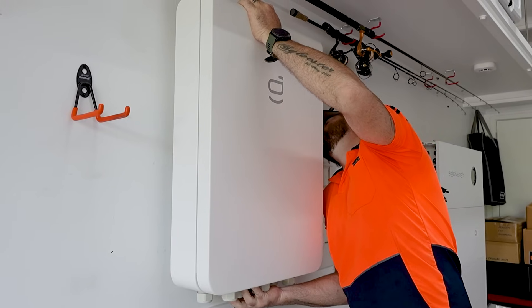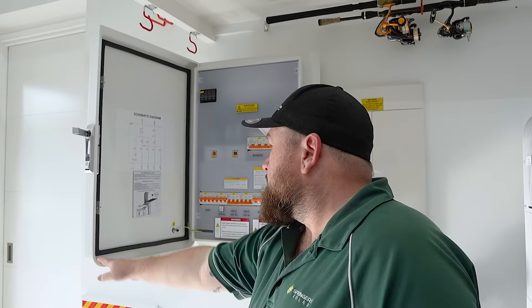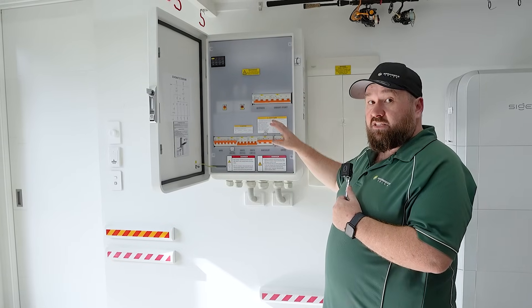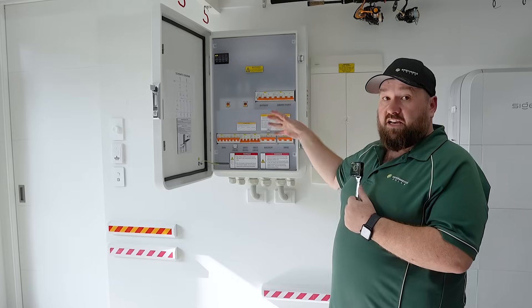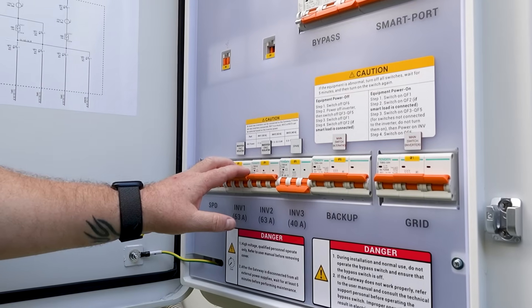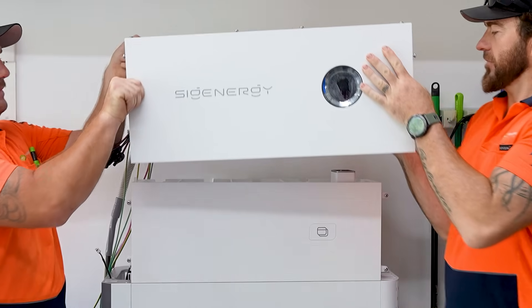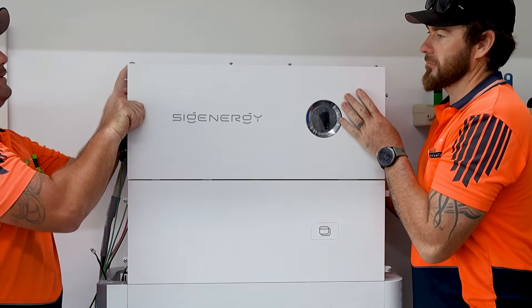The Sigenergy 3-phase backup gateway has an inbuilt bypass or backup switch, so if there's ever an issue, the customer can just come out, flick this switch, and the house will have power coming off the grid as normal. We've also got multiple inputs for multiple inverters, so if we want to add one or two more inverters in the future, we have the ability to do that.